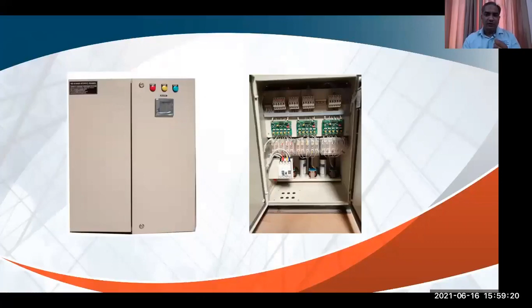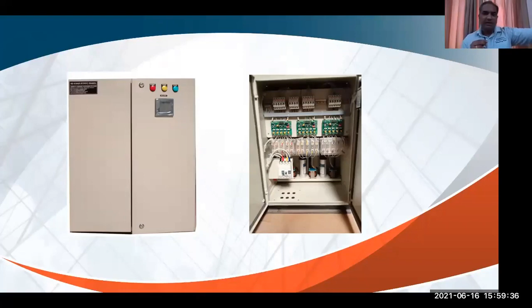So this particular panel I talked about, yeah, this one - we are now giving it to a few panel builders also. So what happens, suppose you have a 500 kVA panel going to an industry, but what about the smaller loads? Will the 500 kVA panel cater to a load as low as 10 ampere or 5 ampere when there is no load, or maybe transformer losses? So this panel can help - the CT side is common, so we can put the CT in the main incomer of this panel. Whenever the load is less, this panel will work. Whenever the load is enough to be taken care of by the 500 kVA panel, that panel will take care of the entire load. So this panel works hand in hand as a hybrid combination.